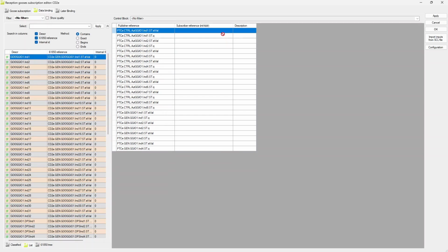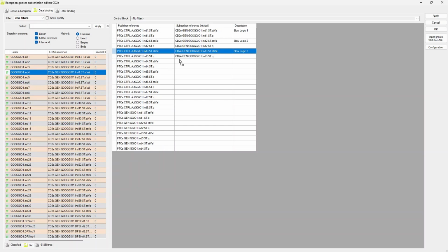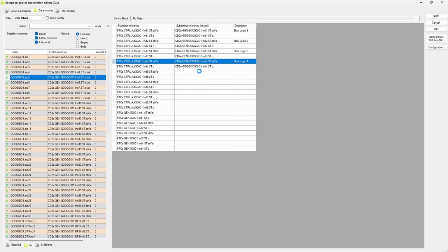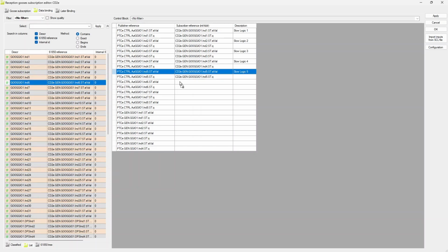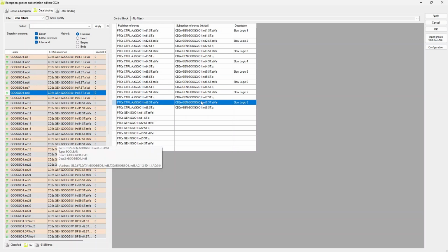On the right hand, with a white background, the data published in the Goose will be displayed. On the left hand, the subscribing IED's IEC 61850 model will be shown. To assign where the published data will be saved in the receiving end's model, the IED's model data can be dragged and dropped into the table on the right. For this subscription, the predefined Goose Data Logical Node, GOOGGIO, has been used. Nonetheless, other model data can also be used as a vessel for the publication's information.